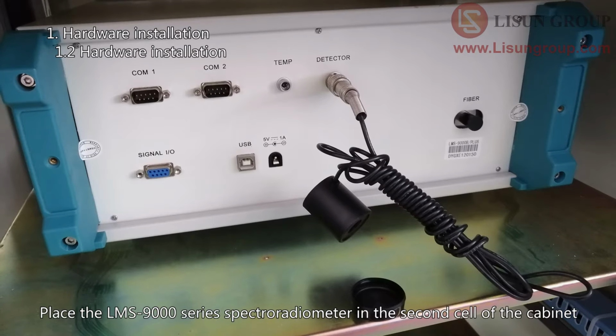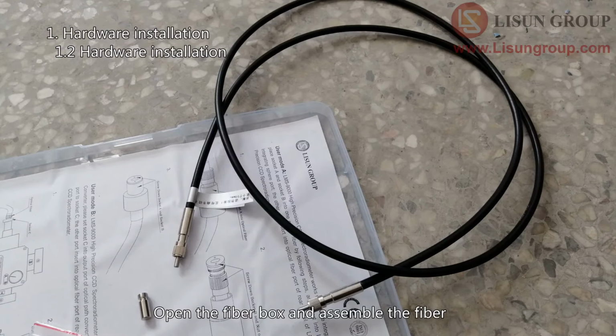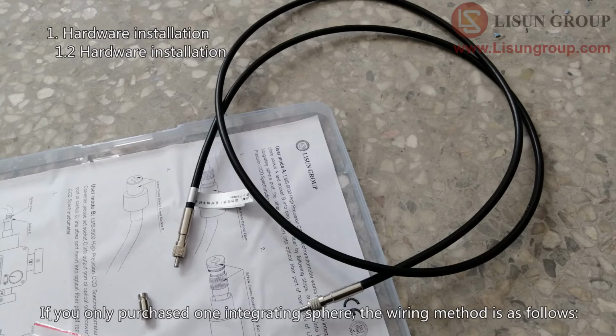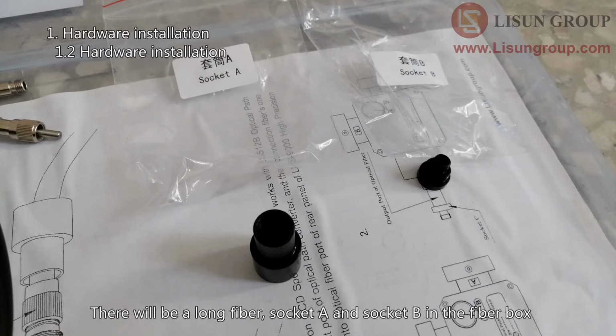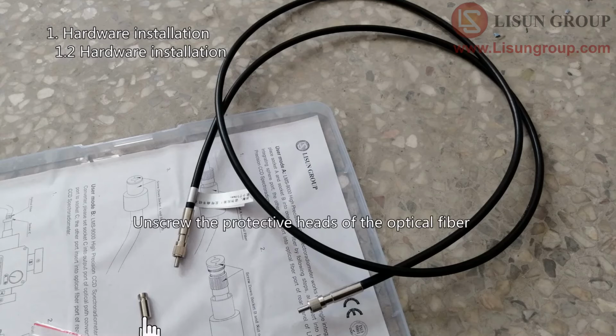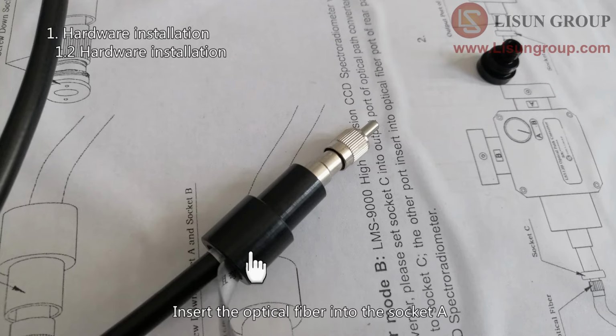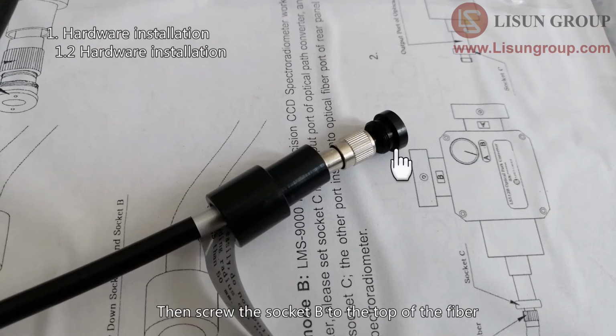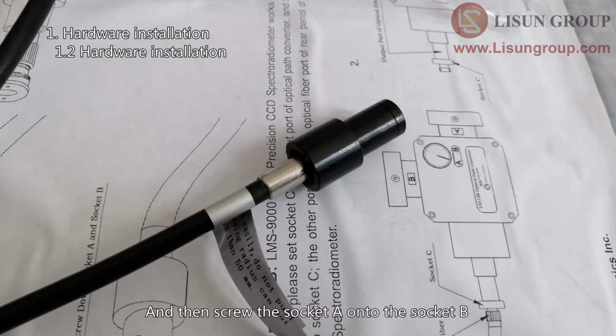Place the LMS-9000 series spectroradiometer in the second cell of the cabinet. Open the fiber box and assemble the fiber. If you only purchased one integrating sphere, the wiring method is as follows: there will be a long fiber, socket A and socket B in the fiber box. Unscrew the protective heads of the optical fiber, insert the optical fiber into the socket A, then screw the socket B to the top of the fiber, and then screw the socket A onto the socket B.